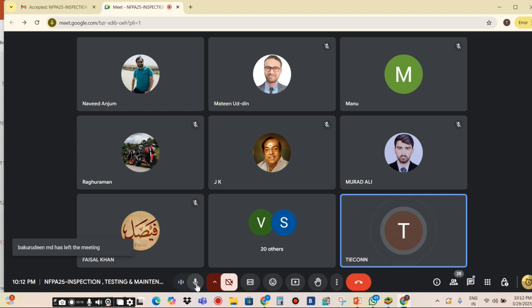If anyone has a question, otherwise I just want to ask one basic question, because I am not the expert in testing and commissioning for NFPA-25. My question to Mr. Naveed, just a basic question, maybe you already know. For example, when we go for spare sprinklers in the fire pump room, when we keep them in the project, if we have different categories of sprinklers, for example, a project with standard coverage, standard response, a K factor of 5.6, and the temperature rating is, let's say, 68 degrees Celsius.